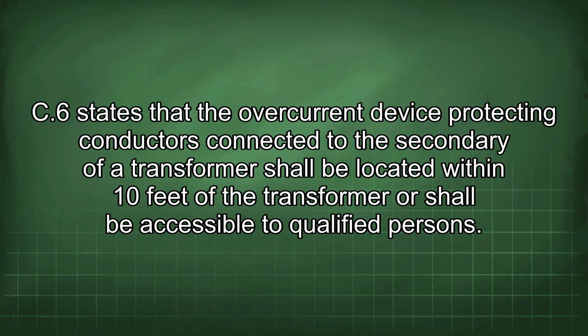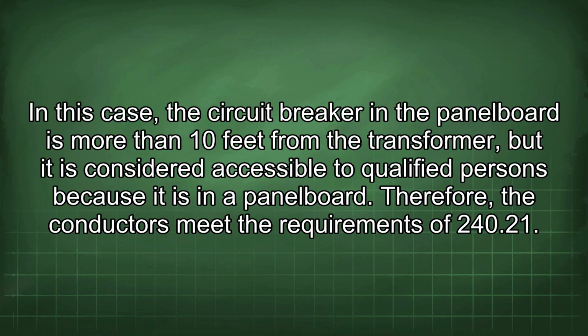240.21(C)(6) states that the overcurrent device protecting conductors connected to the secondary of a transformer shall be located within 10 feet of the transformer or shall be accessible to qualified persons. In this case, the circuit breaker in the panel board is more than 10 feet from the transformer, but it is considered accessible to qualified persons because it is in a panel board.